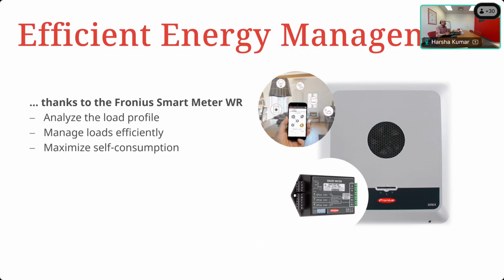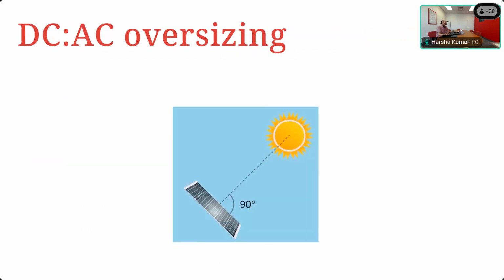Now, the DC to AC oversizing - a lot of you already know what DC to AC oversizing is. I just wanted to throw this in because oftentimes people try to optimize, if you will. What we would rather recommend is that you maximize instead of optimize. If you've got the roof space, why not just go to 150%, simply because it's easier, since your PV panels, PV modules per se, are actually passive.